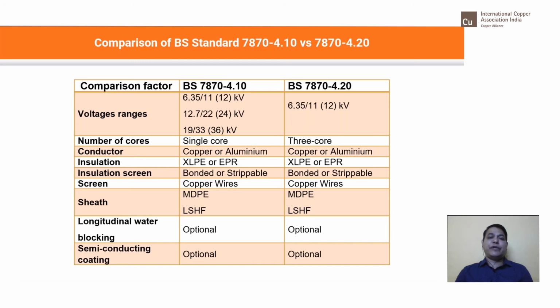They can be with the MDPE sheath. There is no PVC here. You can see that because utilities use them in underground or underground stations, I mean metro stations or railway stations, they probably use MDPE sheath because of its ability to not absorb water when they are placed in water exposed areas. So MDPE is so important because it is water resistant, some kind of. Low smoke zero halogen is important when it is installed within the building.